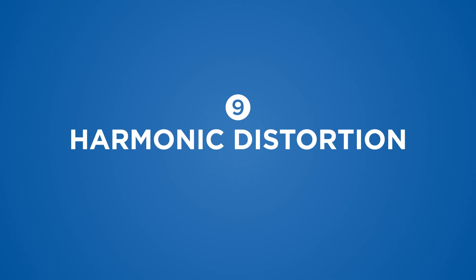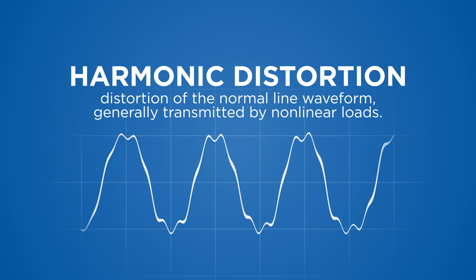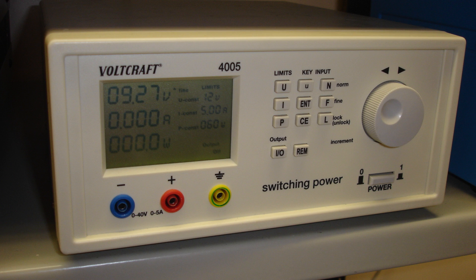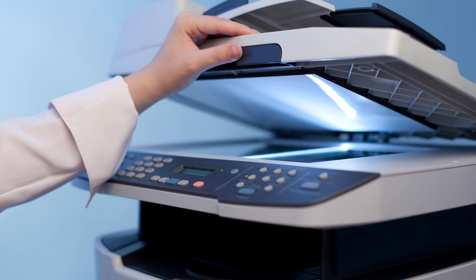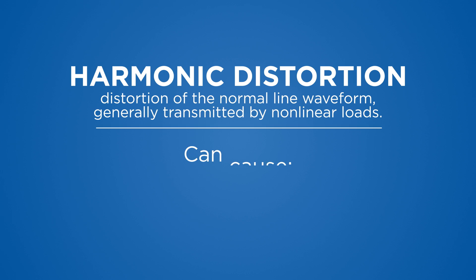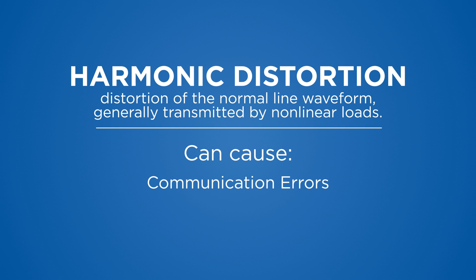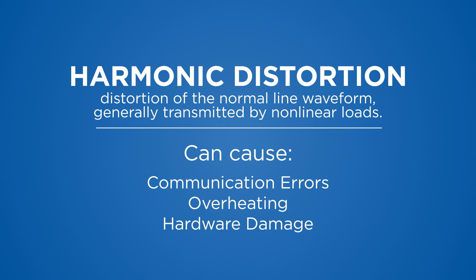Harmonic distortion is distortion of the normal line waveform, generally transmitted by nonlinear loads. It is caused by switch-mode power supplies, variable speed motors and drives; copiers and fax machines are examples of nonlinear loads. This type of power problem can cause communication errors, overheating, and hardware damage.